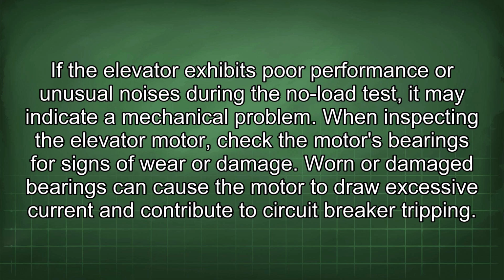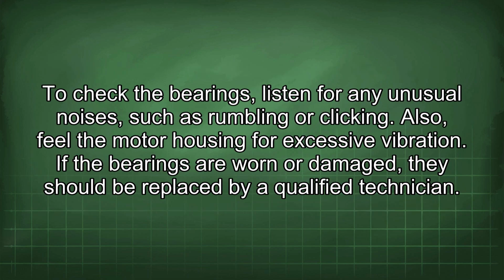When inspecting the elevator motor, check the motor's bearings for signs of wear or damage. Worn or damaged bearings can cause the motor to draw excessive current and contribute to circuit breaker tripping. To check the bearings, listen for any unusual noises, such as rumbling or clicking. Also, feel the motor housing for excessive vibration. If the bearings are worn or damaged, they should be replaced by a qualified technician.